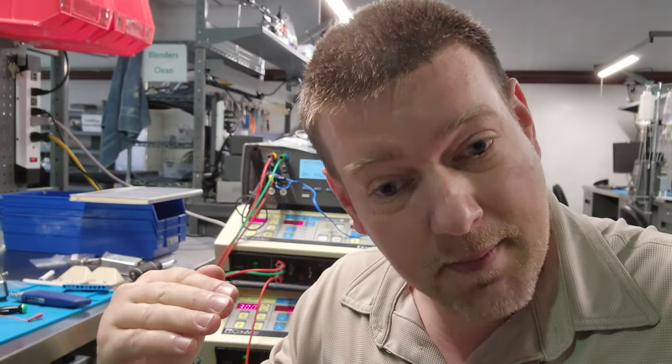That way if you shut the device off and it boots up with the last known settings, they're at the minimum and the doctors and nurses have to increase the output in order to get the desired effect. If they start at the maximum when they're expecting minimum, they're gonna burn somebody and somebody's gonna get hurt. Thanks for watching.